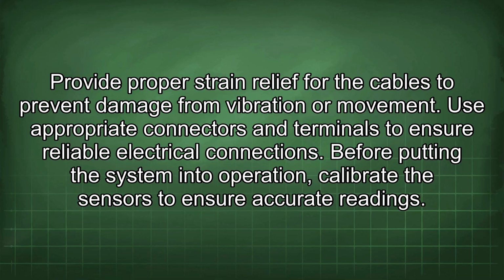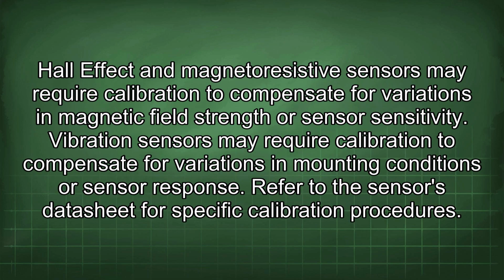Before putting the system into operation, calibrate the sensors to ensure accurate readings. Hall effect and magnetoresistive sensors may require calibration to compensate for variations in magnetic field strength or sensor sensitivity. Vibration sensors may require calibration to compensate for variations in mounting conditions or sensor response. Refer to the sensor's datasheet for specific calibration procedures.